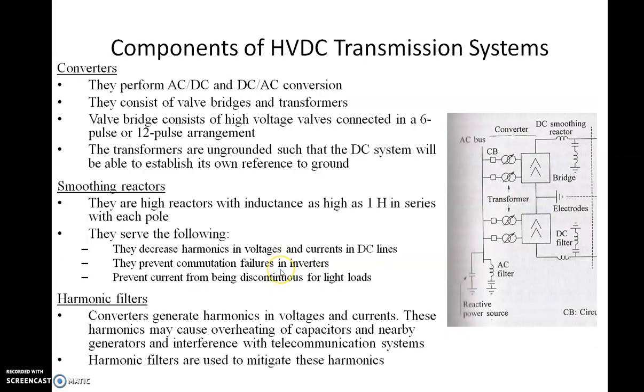A quick overview of the devices: converters perform AC-to-DC and DC-to-AC conversion. They consist of valve bridges and transformers. A valve is like a water valve — if you open it, current flows; if you close it, current cannot flow. Using a number of valves together forms a valve bridge. Converters consist of high-voltage valves connected in a 6-pulse or 12-pulse arrangement. The transformers are ungrounded so that the DC system can establish its own reference to ground.